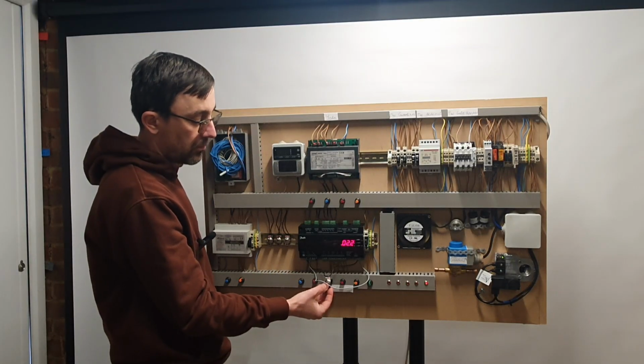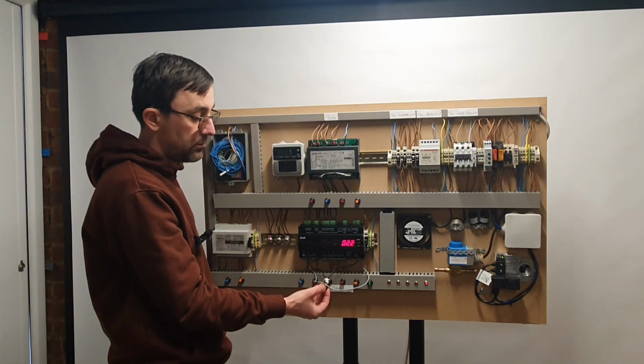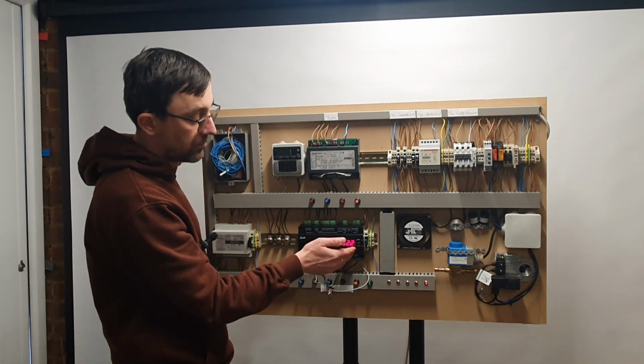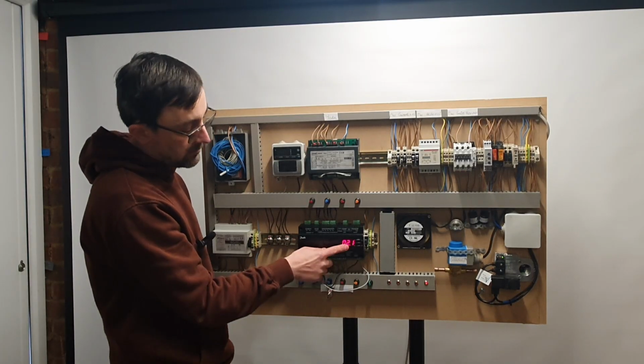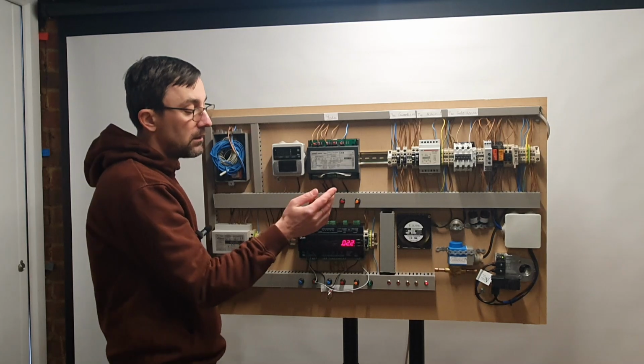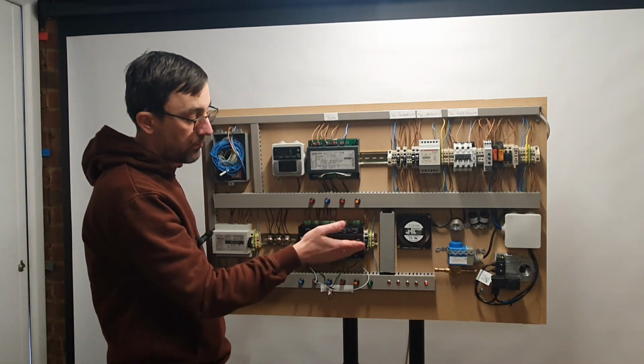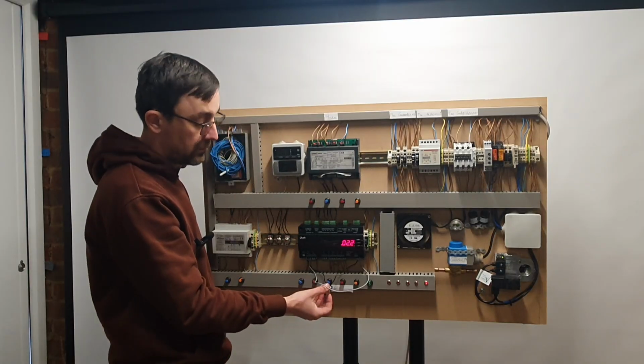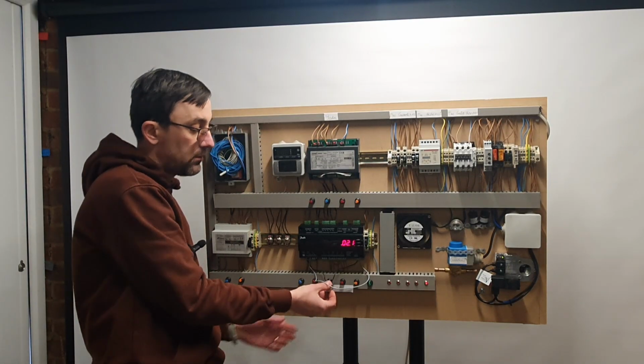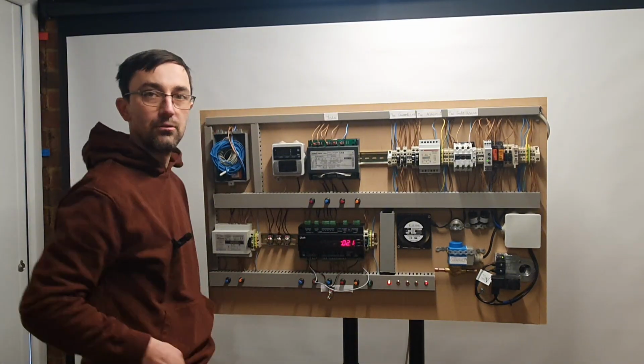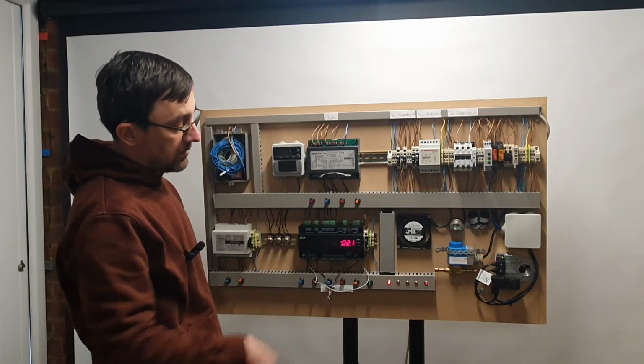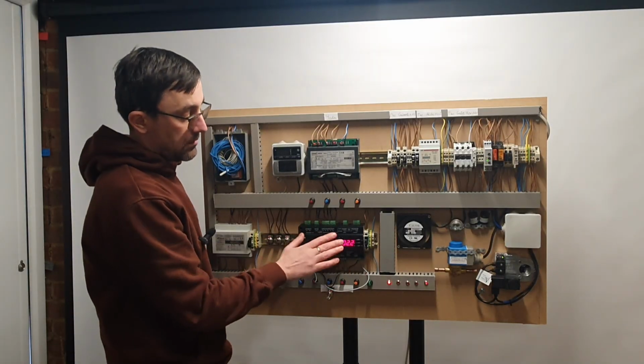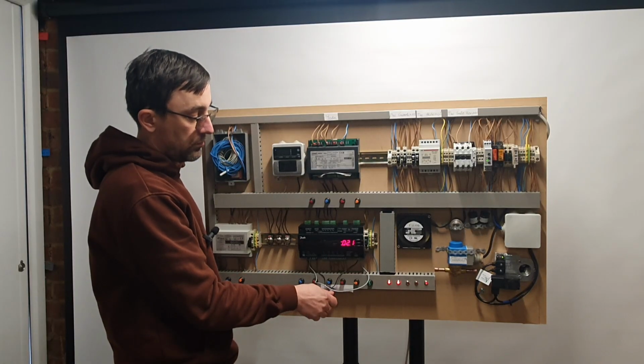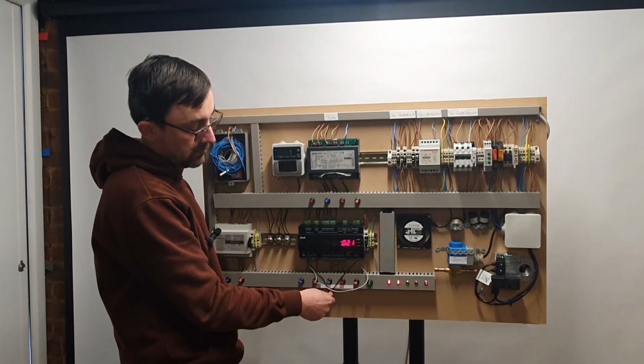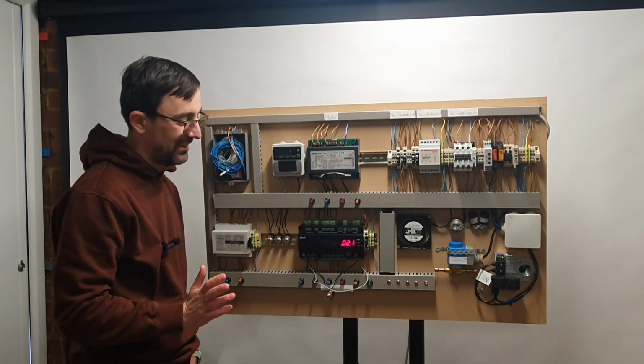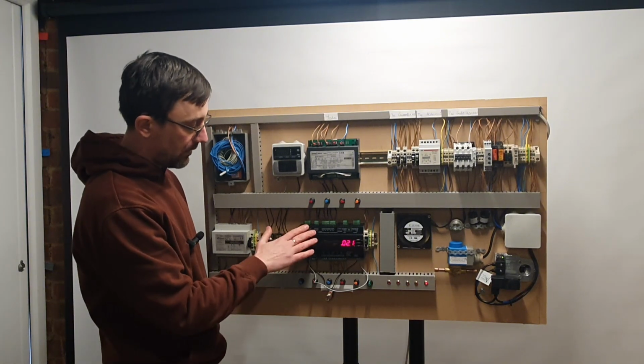So now I'm on the on position for my switch. So I have 230 volts going into my digital input. Temperature is 2.1 degrees. The set point for my thermostat band number 2 is 3.5. So it doesn't want to refrigerate. Then if I switch over to band number 1, which has a set point of 0 degrees, it wants to refrigerate. It has a differential of 2 degrees. So yes, it will do that. So now let's switch over to a set point of 3.5 degrees. You stop. So finally, we managed to configure correctly all 3 digital inputs.